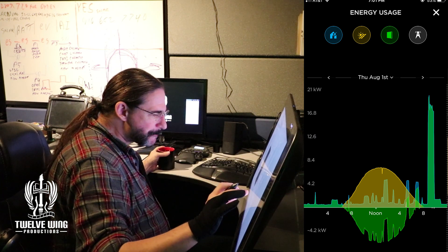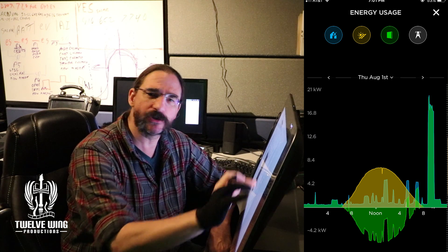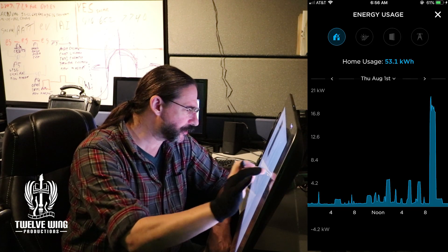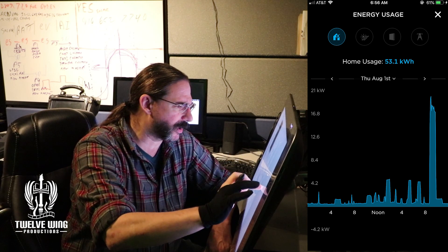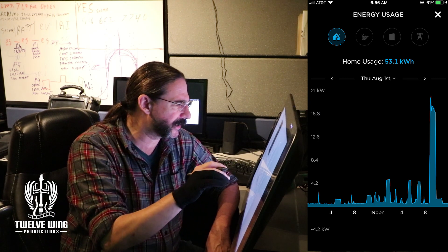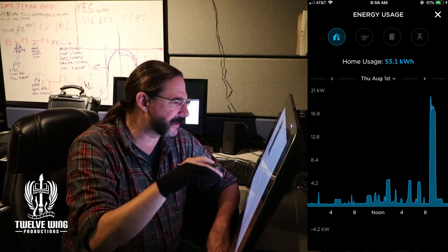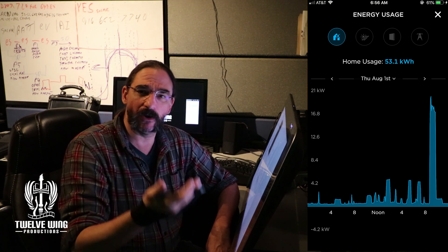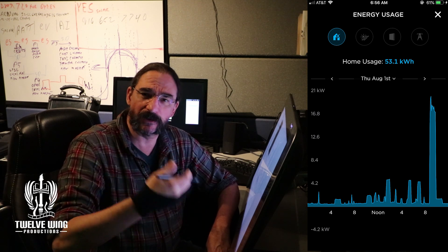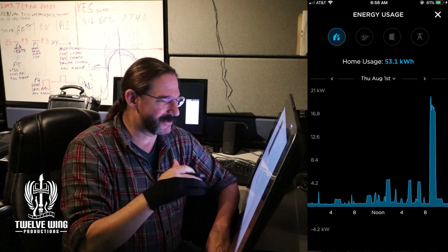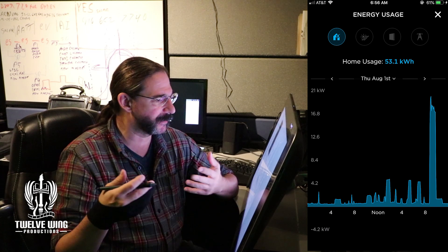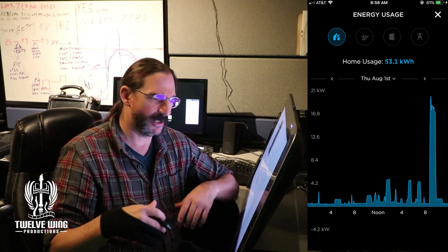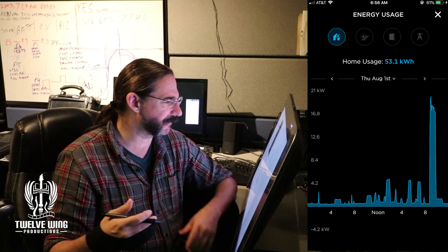The first thing let's look at is the home usage alone. This shows the raw usage of the home and you can draw an imaginary line across the bottom of the graph that the blue never dips below. This would represent about a 0.6 kilowatt baseline load of the home, which is simply a load that the home always has. It represents things like a pond pump, some lights in the home that are on constantly, downstairs TV is on almost 24/7.